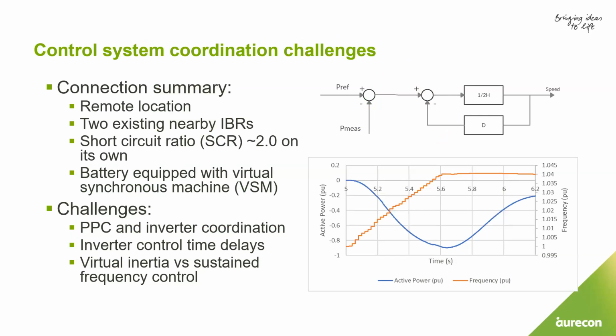So let me share practical experience with grid forming inverters, based on a virtual synchronous machine. It's a very big part of the network. The SCR at the connection point, at the inverter terminal, is marginally above 1. There are other inverter-based resources, so this SCR of 2 I'm quoting is on a single unit basically. This is the way of implementing the swing equation, which again is not surprising.